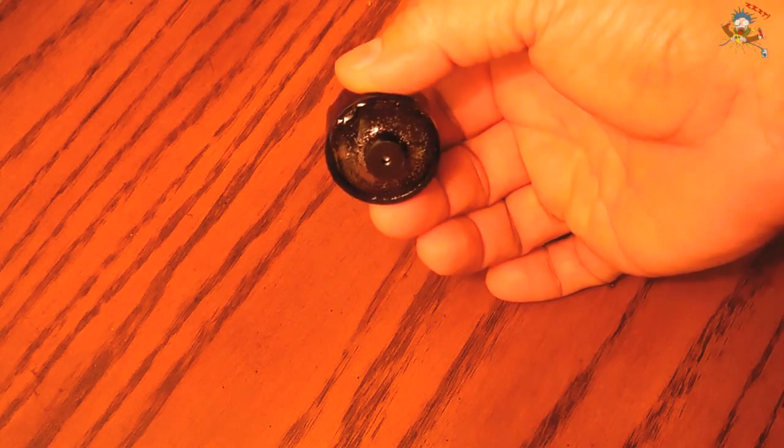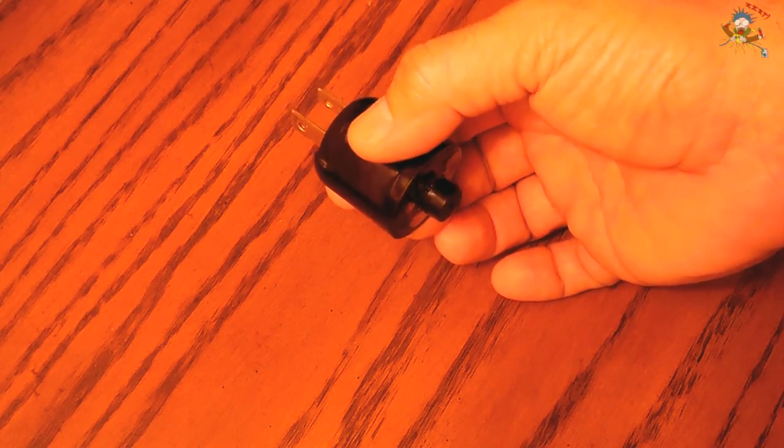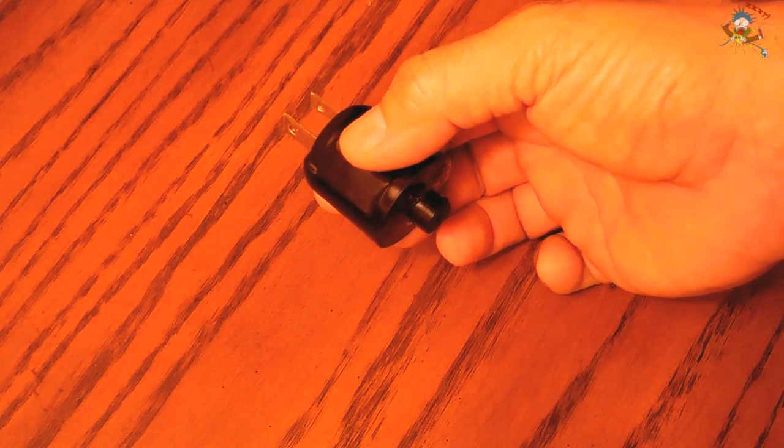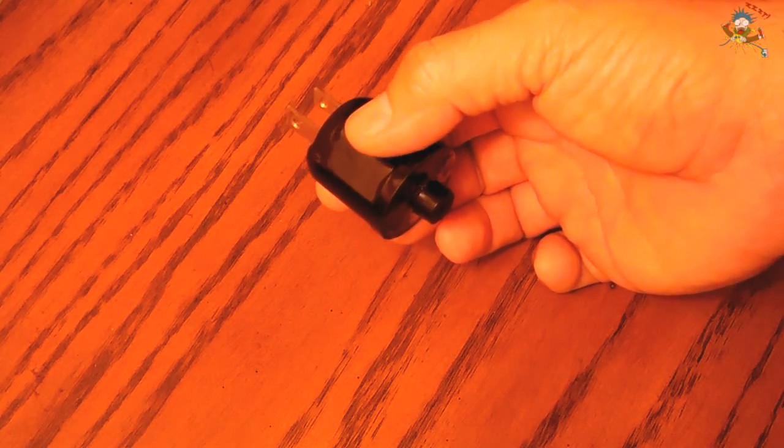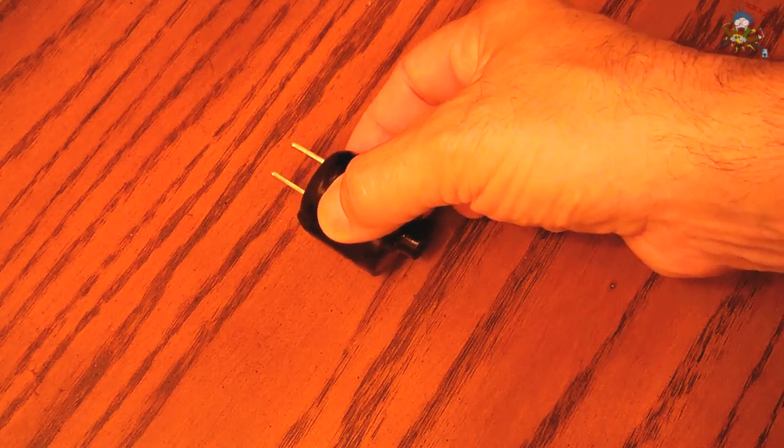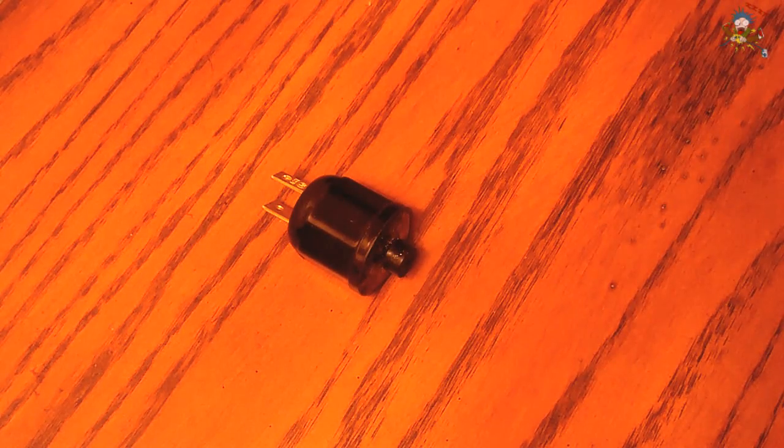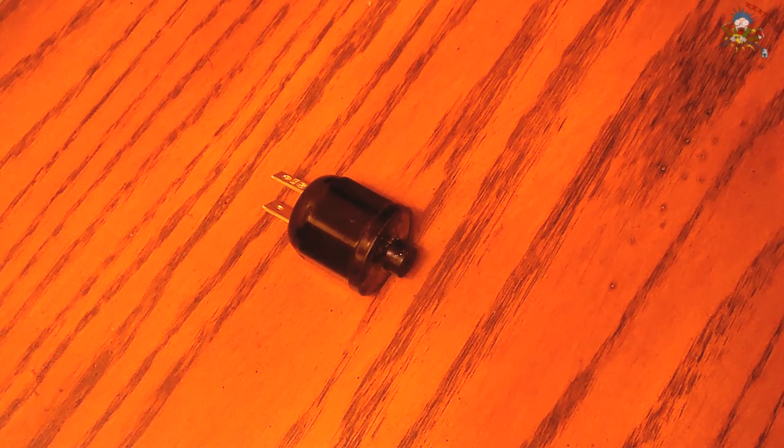Once you plug this in, this loud piezo alarm is going to sound, and it is very loud. Once the alarm sounds, you can then go to the electrical panel, and then turn off the circuit breakers one by one until the piezo alarm goes off. You will then know the circuit is off, and you can work on it.